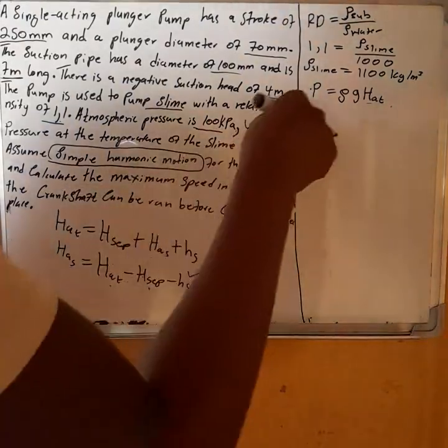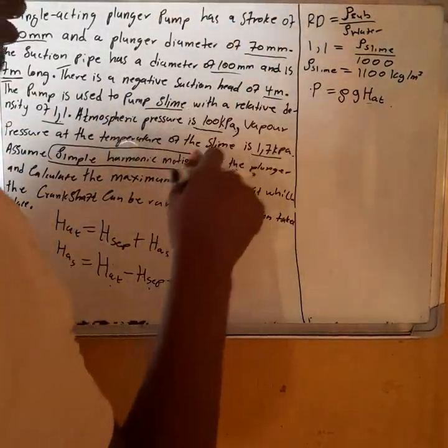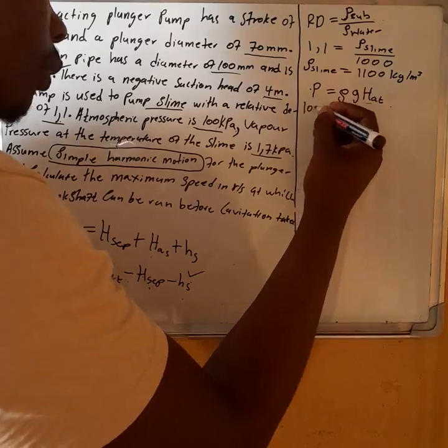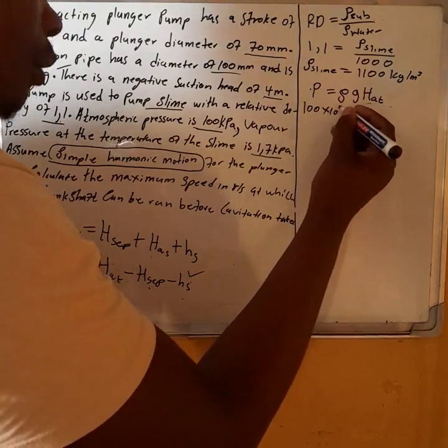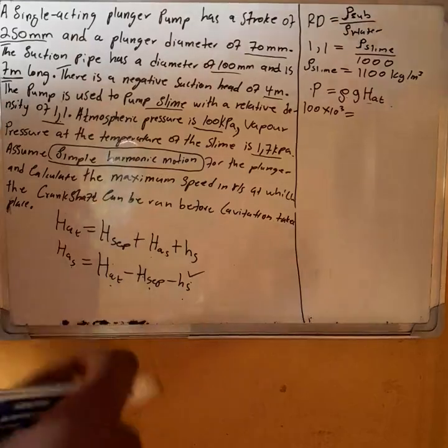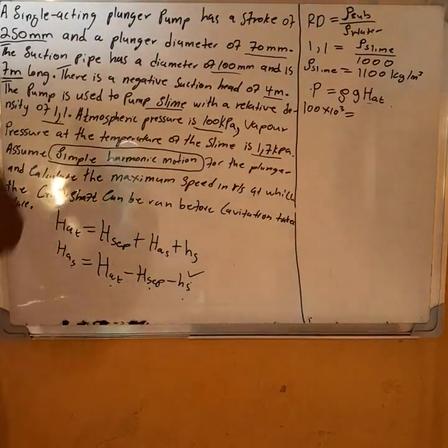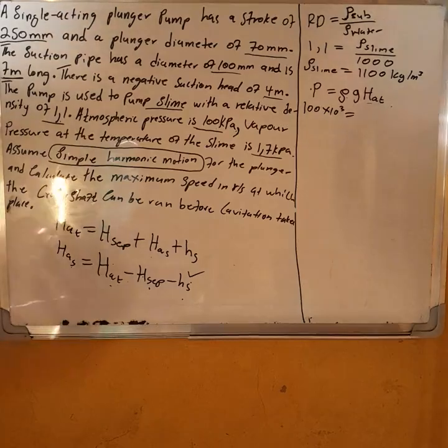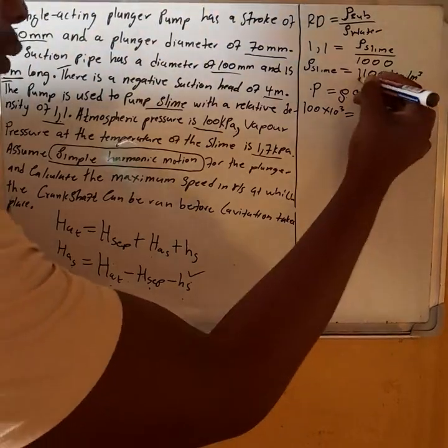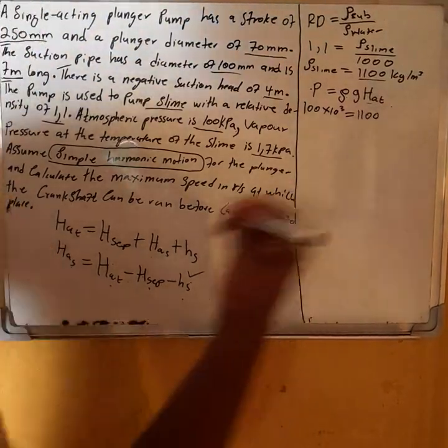So you substitute the pressure, which is 100, multiplied by 1000 because it's in kilos, in SI units, 100 times 10 to the power 3. The density will be the same. We're using the same liquid throughout, the slime that we are supplying the pump. It's the same throughout. This is the density we have calculated here, 1100, right?